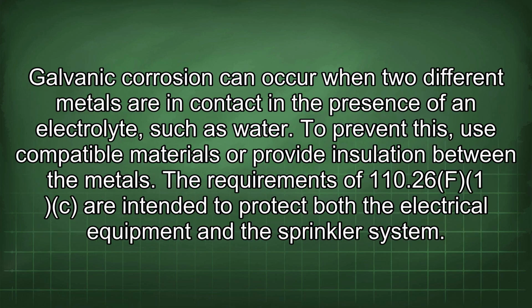piping system. Galvanic corrosion can occur when two different metals are in contact in the presence of an electrolyte such as water. To prevent this, use compatible materials or provide insulation between the metals.